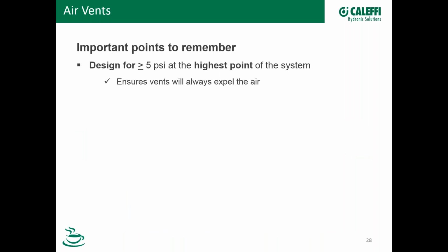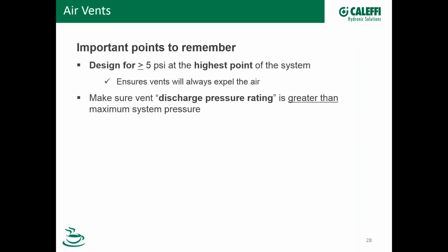All right, let's summarize air vents. There are a few things really to take away from this. Make sure you design your system so that you always have at least 5 PSI at the highest point of the system. We want to make sure that the vents will always expel air. We don't want to draw a vacuum up there or anywhere where you locate a vent. We want to make sure that the discharge pressure rating, now this is a spec item, make sure that the vent you're selecting has a discharge pressure rating greater than what you will see in your system, because if the system pressure is higher than the discharge pressure rating, what happens is the little needle valve will be held closed so that no air will escape from the system. So just make sure you check that.